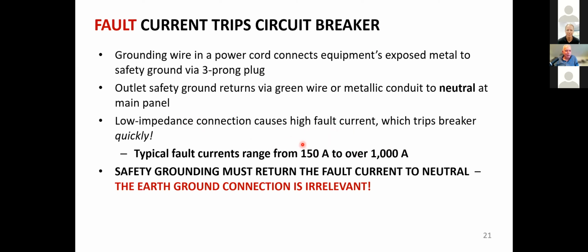On 100-foot runs, it'll be closer to 150 amps. But if you get one that's only a foot or two away from the breaker panel, it could easily hit 1,000 amps. You throw a short across your incoming electric service, and you're likely to see several thousand amps before anything happens. So this happens independent of any earth connection.